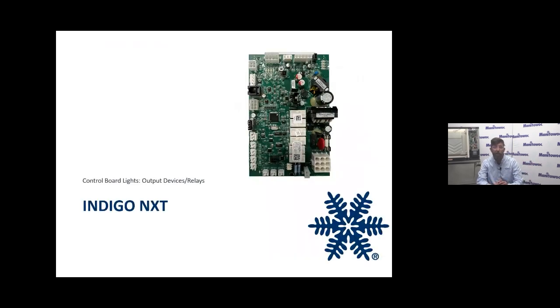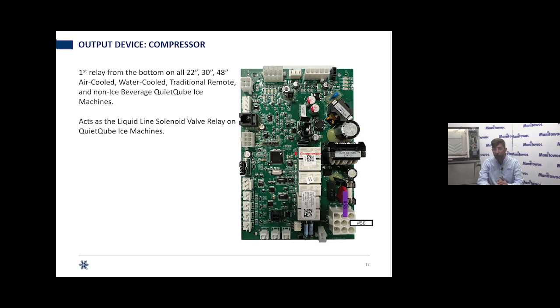All right, so output devices. Notice previously on those input devices, all those lights were green. On output devices, these lights are going to be red. So the compressor relay, keep in mind on machines where the compressor is inside, we are actually sending voltage to the contactor coil. And that red LED next to it, that's a predetermined response. When it is time to energize that relay, that LED lights up. That does not guarantee that we are sending power from that relay to that contactor.